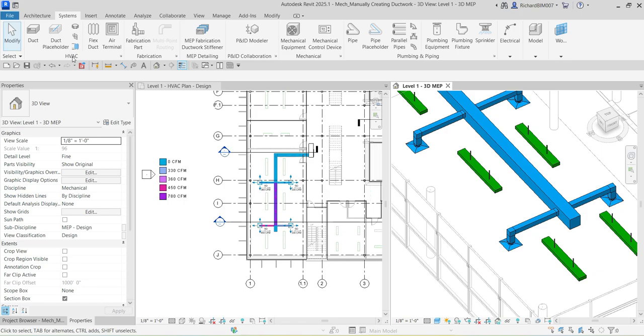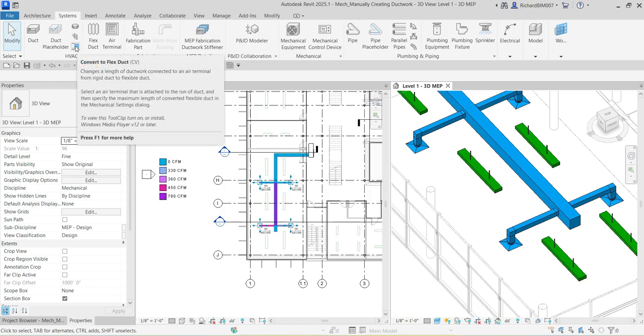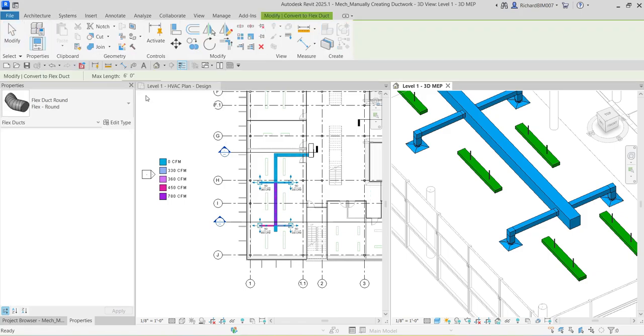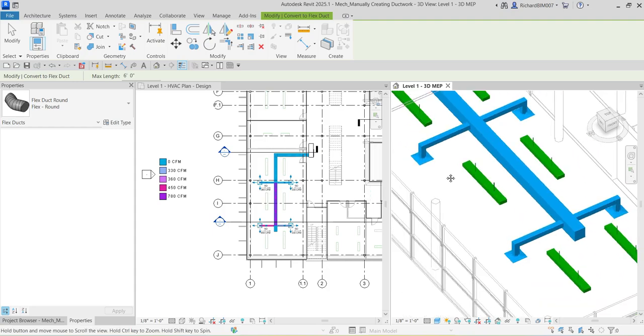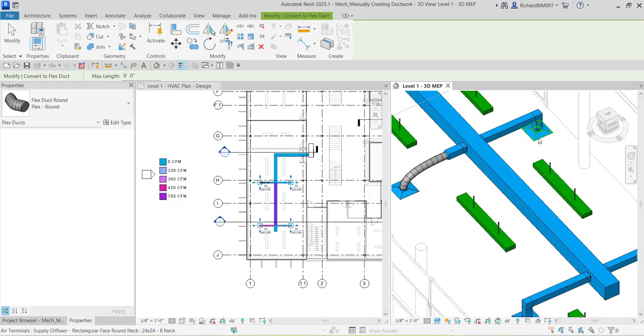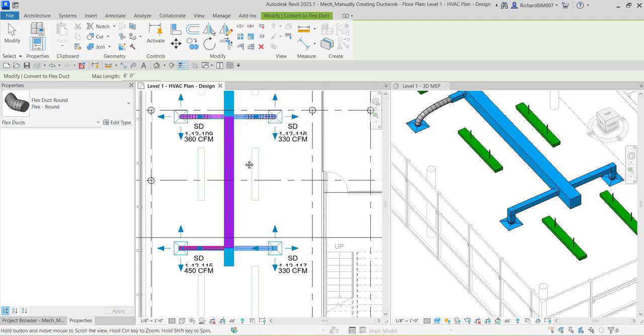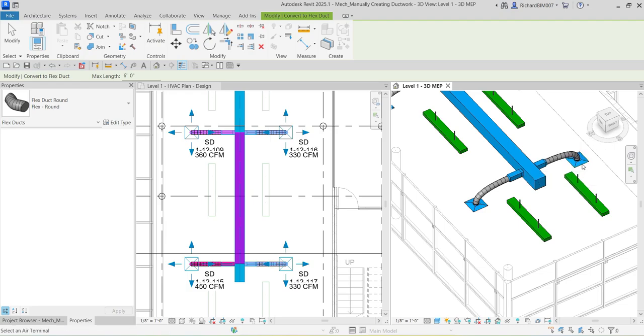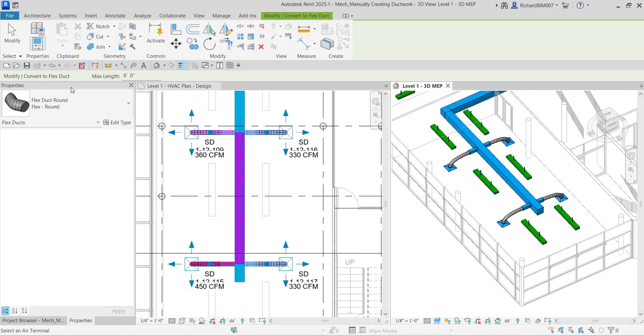To convert to flex duct, go to the Systems tab, find the HVAC panel, and look for the 'Convert to Flex Duct' tool (shortcut: CV). It changes a length of ductwork connected to an air terminal from rigid duct to flexible duct. Click the tool, then select the air terminal — not the duct. You can do this in the floor plan view or the 3D view. Click the air terminals to convert them to flex duct, then select Modify. Your floor plan view updates automatically.